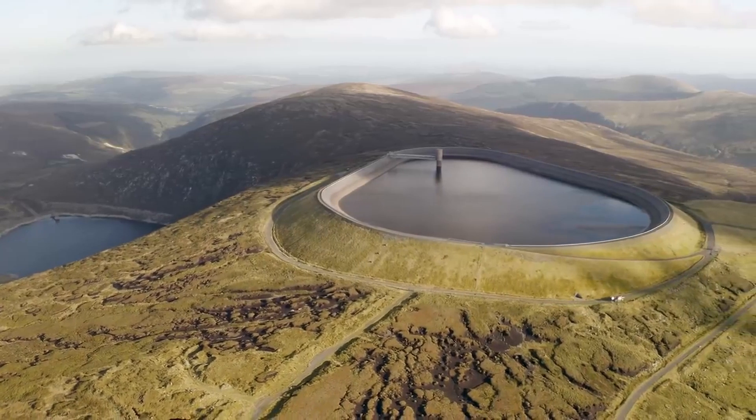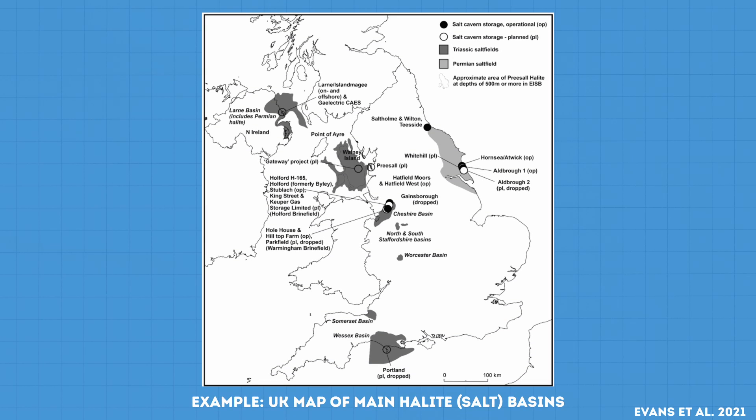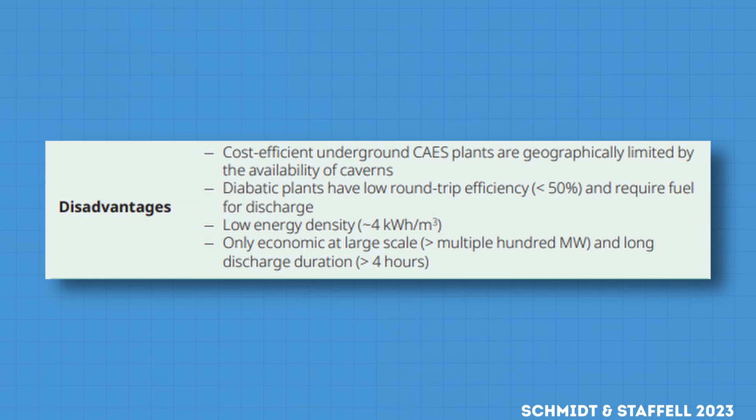Compressed air energy storage is normally only economical at large scale and longer discharge durations, which is why it's quite similar to pumped hydro storage. As for the cons: firstly, it's quite location dependent, requiring good geological formations such as salt caverns. However, if air is stored above ground in tanks, this is not an issue — the underground option may be cheaper but is constrained to a few locations, whilst tanks are more expensive but can be modularized and placed anywhere. Due to CAES having a low energy density, the size of projects can make financing a challenge.